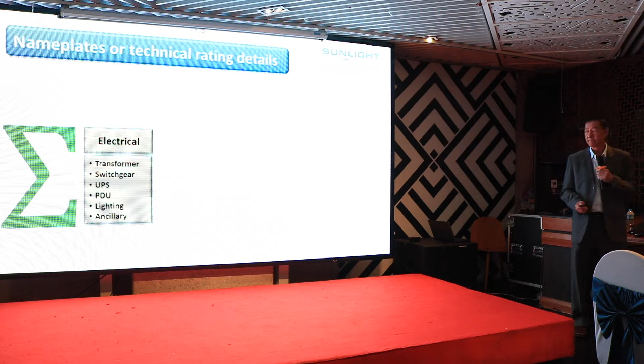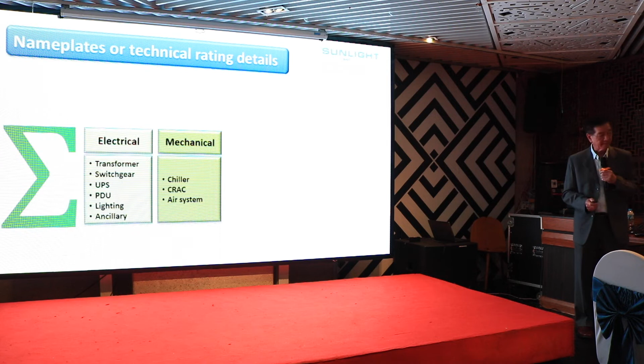So for all the equipment, one way to do it is to go and take the nameplate, all the technical details, the technical catalogs of the equipment that will be installed and chosen for use in the data center. You sum up the power - the electrical part: what are the transformer losses, the switchgear, UPS, PDU, lighting, and any other auxiliary services in the building. For the mechanical side: the chiller, the CRAC, the air system.